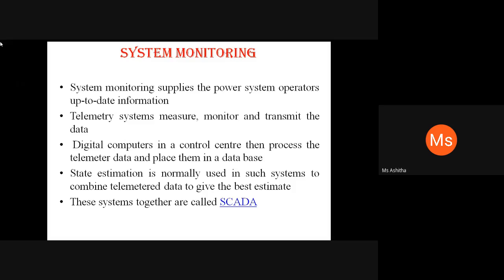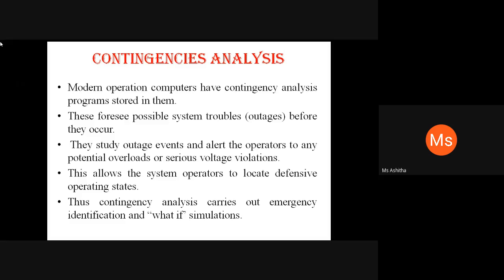Such systems often work with the superior supervisory control system to help the operators control the circuit breakers and operate switches and the taps remotely. Such systems are together called SCADA system, supervisory control and data acquisition system. The second major security function is contingency analysis. Modern operation computers have contingency analysis programs stored in them. These foresee possible system troubles before they occur. They study outage events and alert the operator to any potential overloads or serious voltage violations, etc.